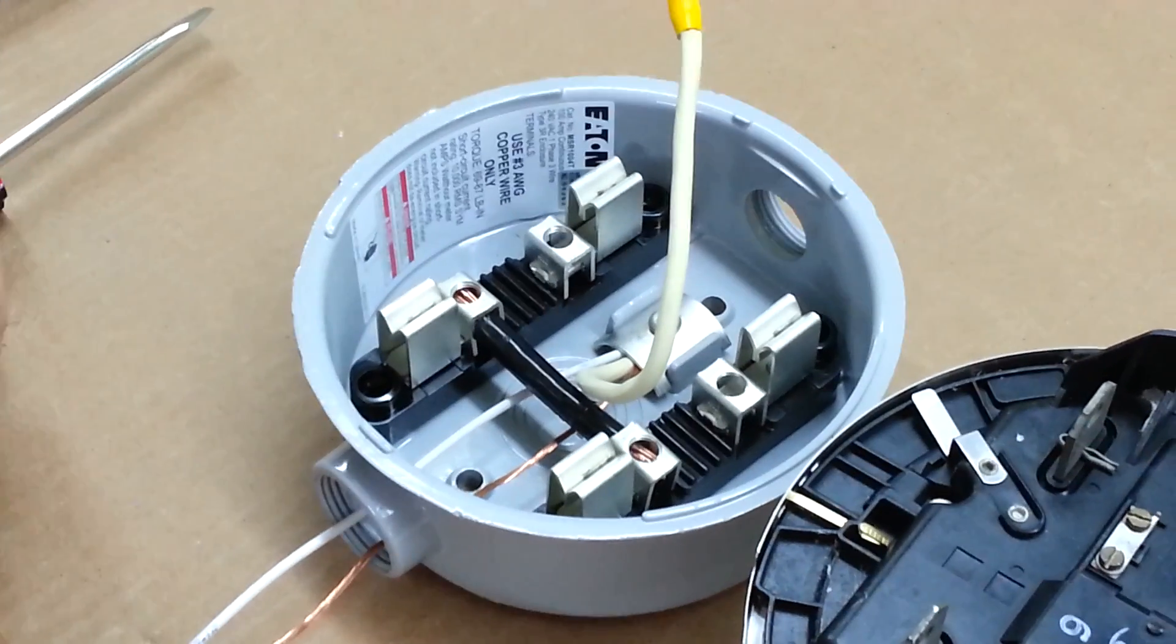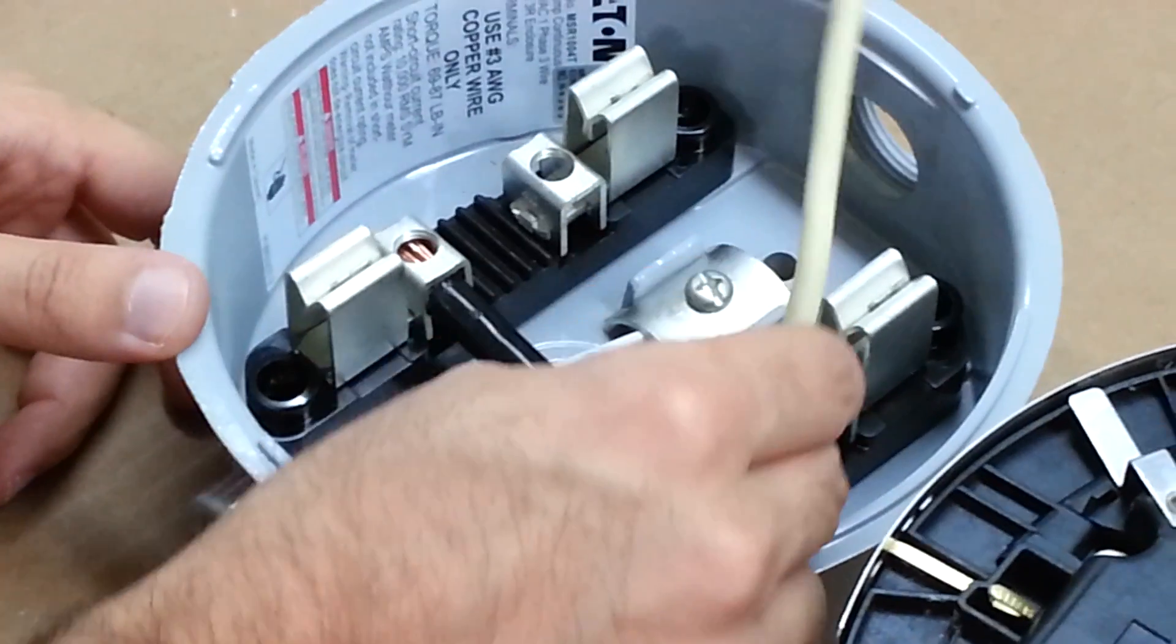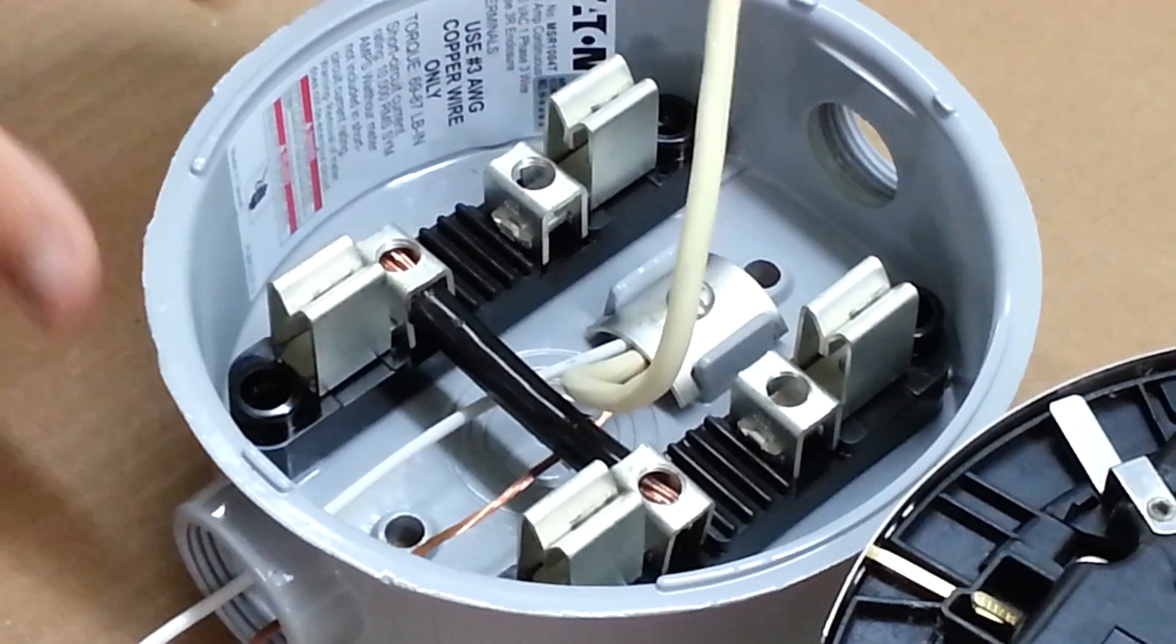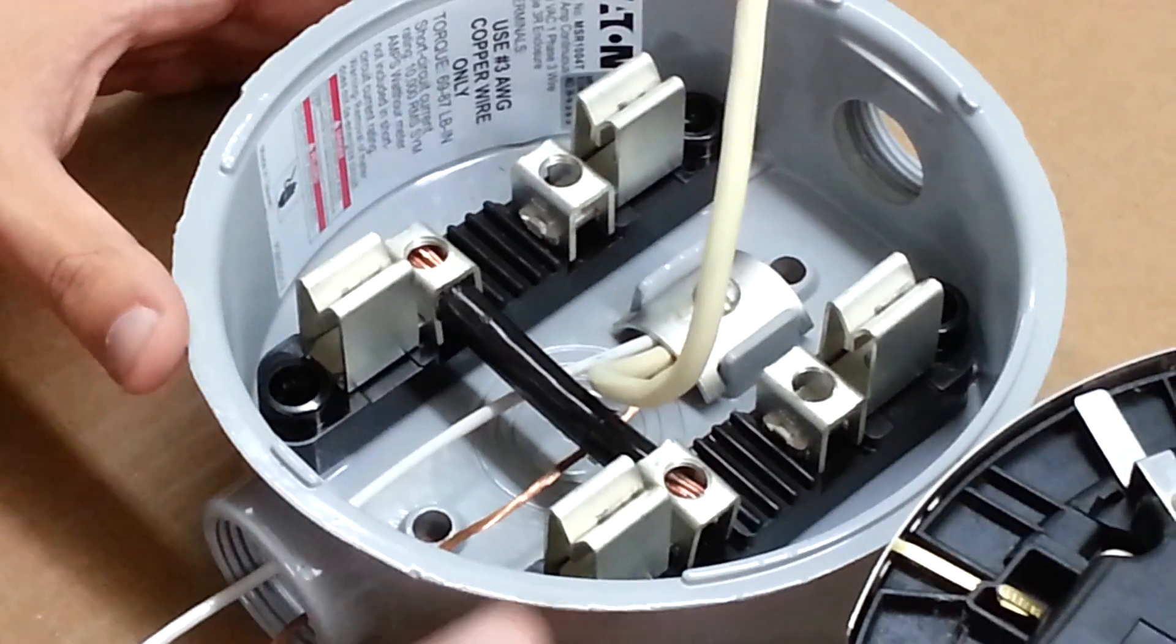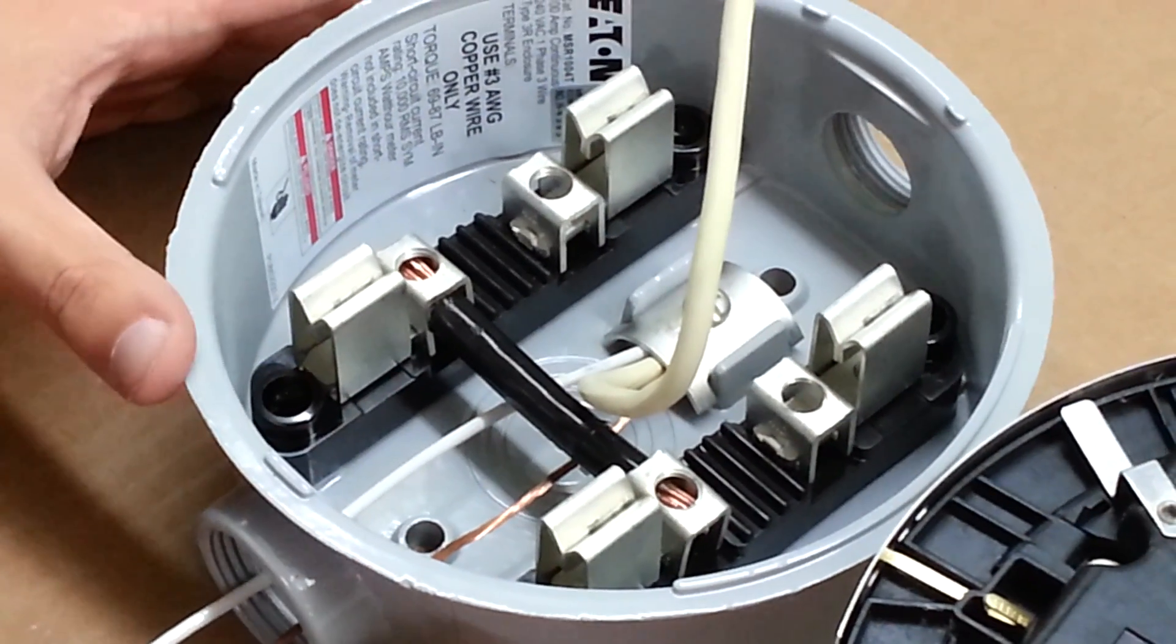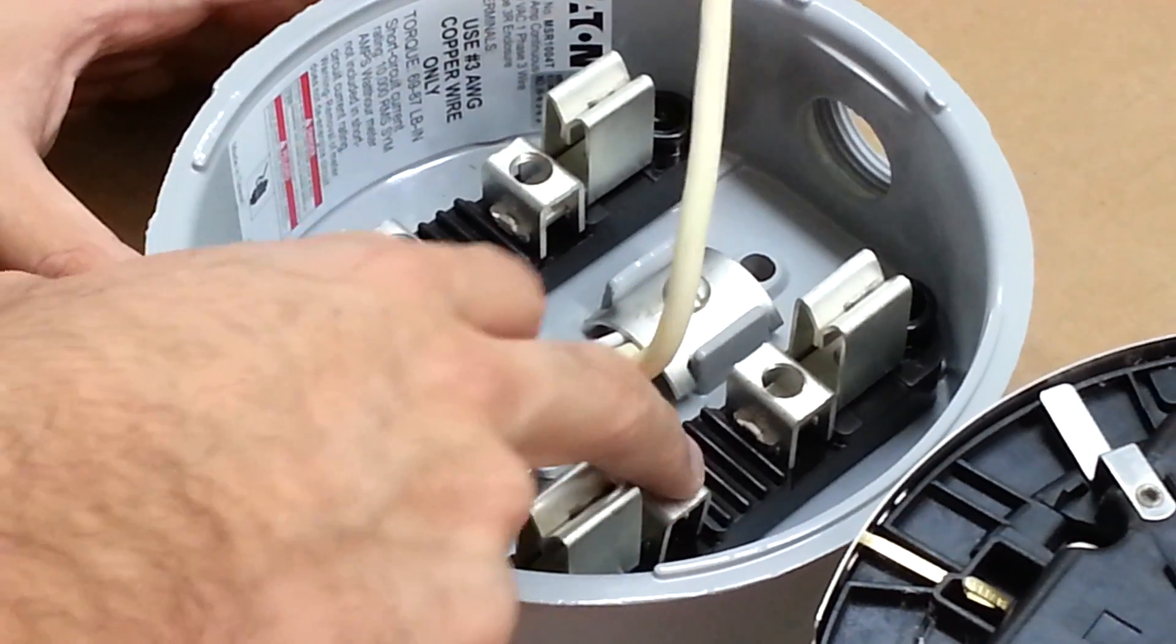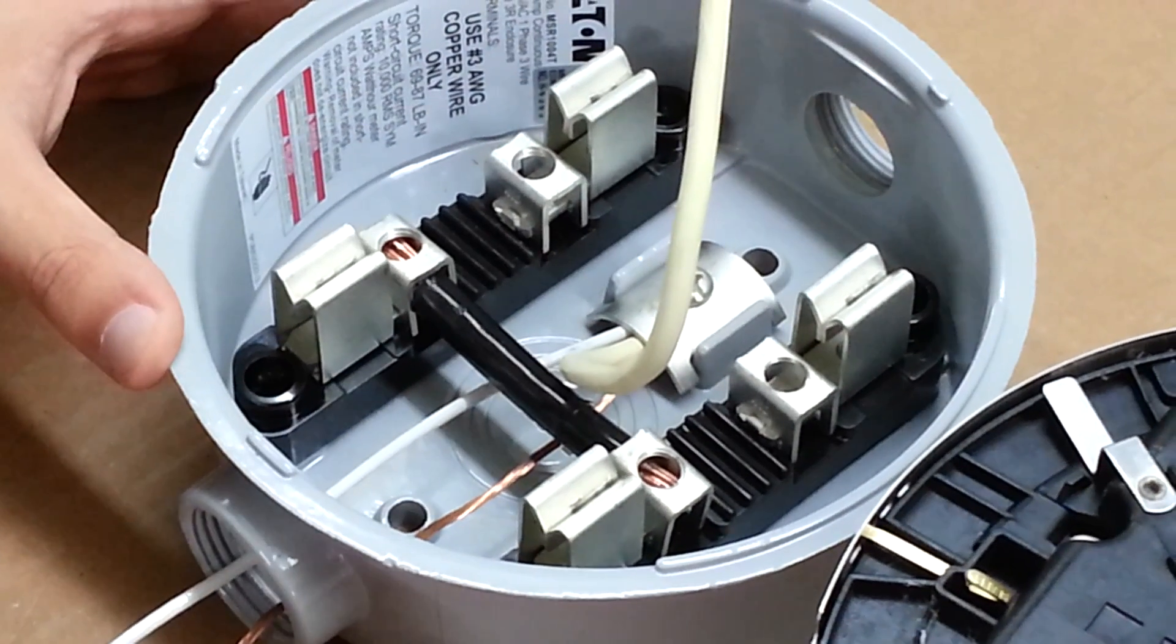We are also going to use a jumper wire to connect to the back of the meter. It is very important that the neutral and the ground are connected together for safety purposes. We also need to include a jumper wire for the two bottom lugs of the socket.